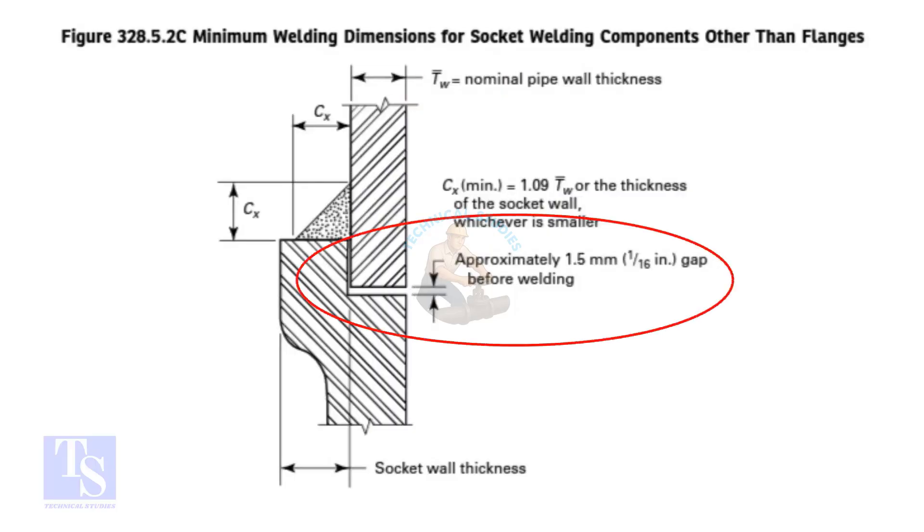In the drawing, a gap is shown between the fitting and the pipe end. The purpose of this clearance in a socket weld is to reduce the residual stress at the root of the weld that could occur during the solidification of the weld metal. It also allows for the expansions and contractions that happen during service.